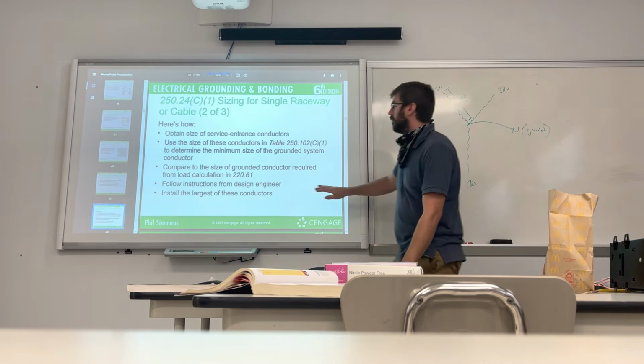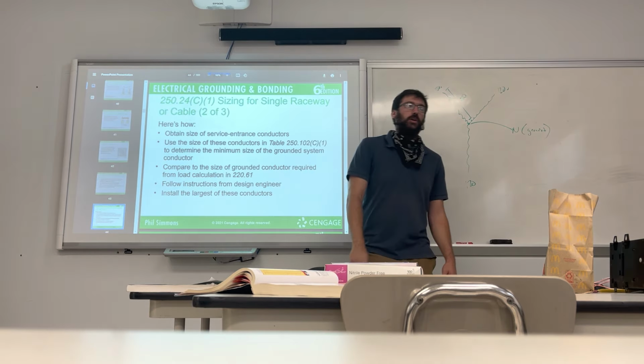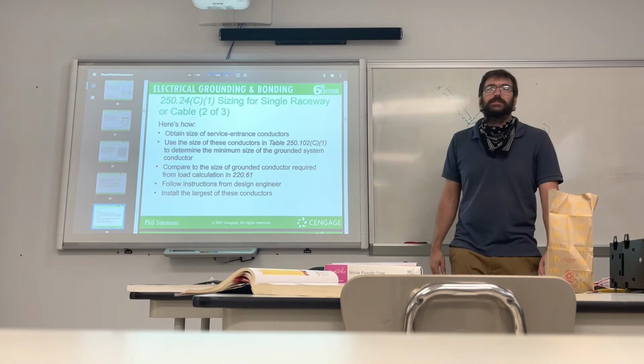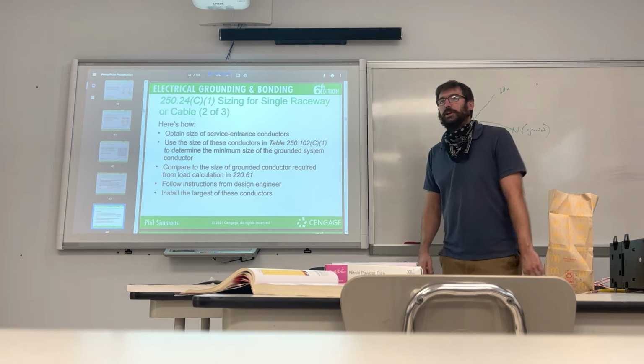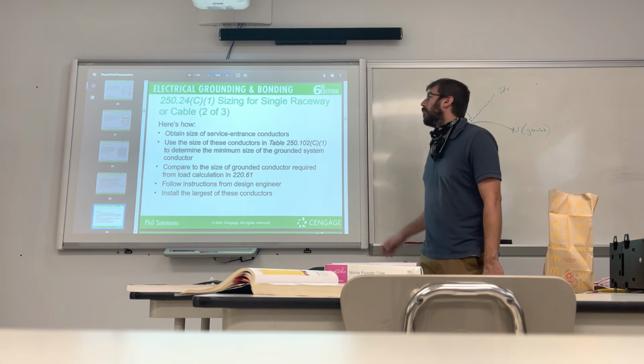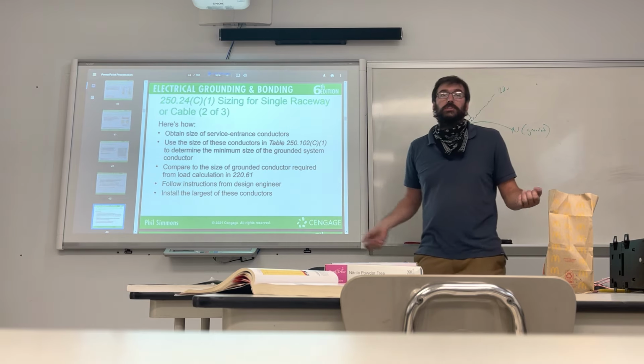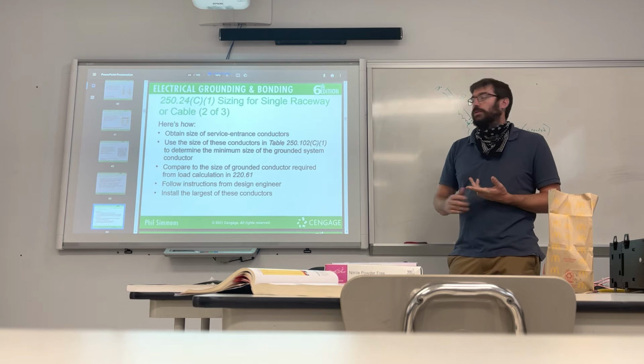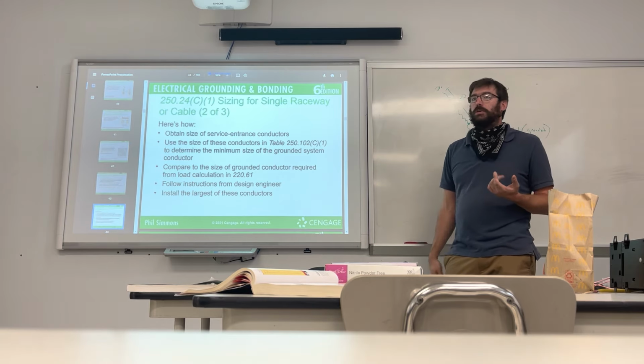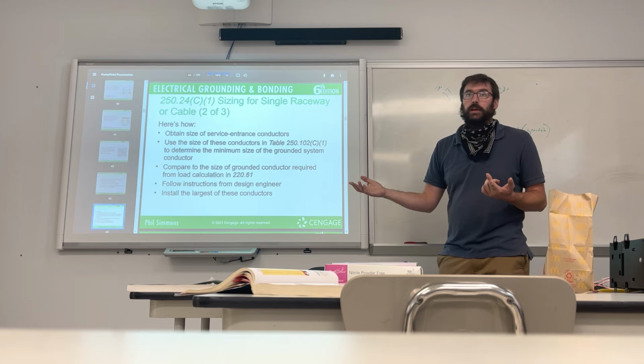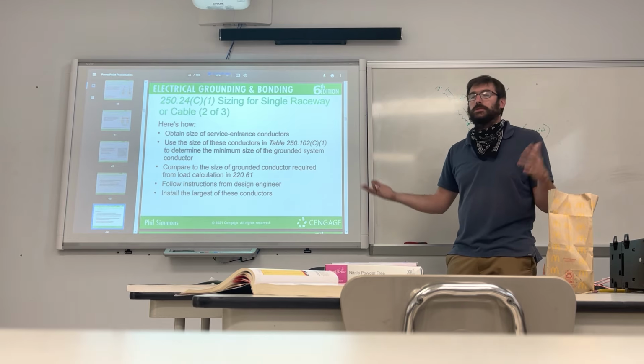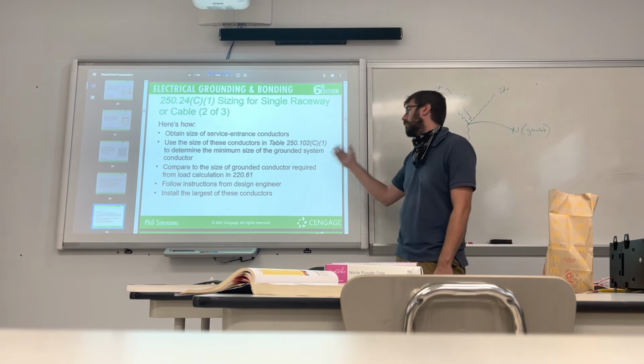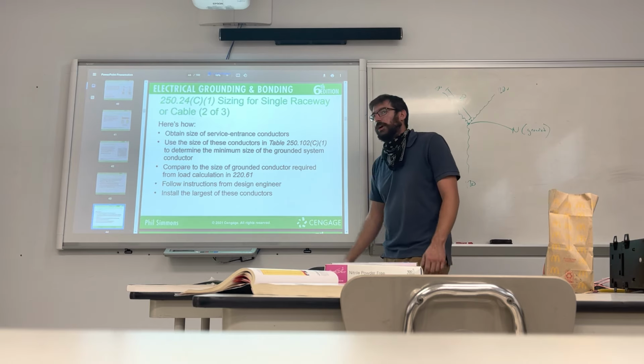Now, apart from consulting the engineer, which I will never openly admit to doing, because we're electricians, we don't like engineers. But this is basically what I've been telling you. You're gonna take a look at your service coming in, which tells you the size of the conductors, but we already know how many amps are coming in, and the size of the conductors based on those amps. So we just take a look at the table and go from there.